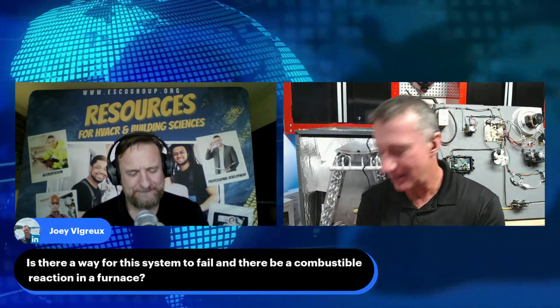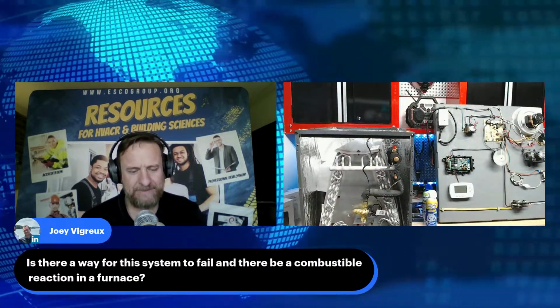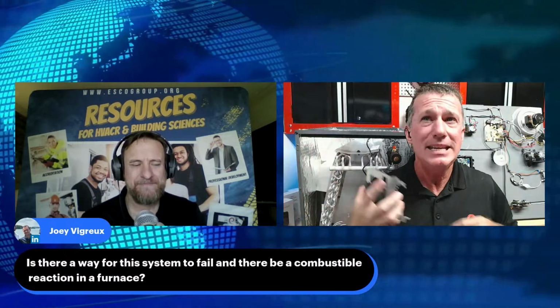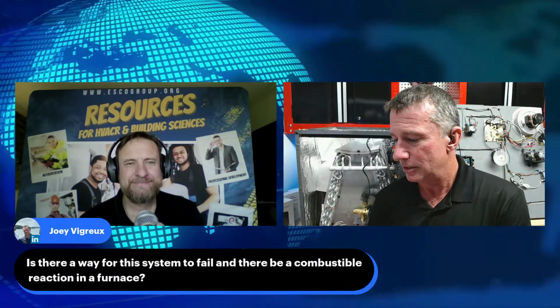Edit. And within 5 seconds, my control board has recognized that my refrigerant detection sensor is not connected to the control. And so it now immediately goes into its state of mitigation as an additional step of protection for that. And if you haven't seen our video, Joey, on the flammability of these gases, it's very disappointing.